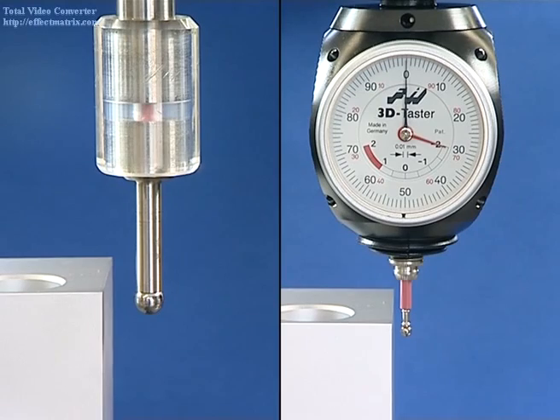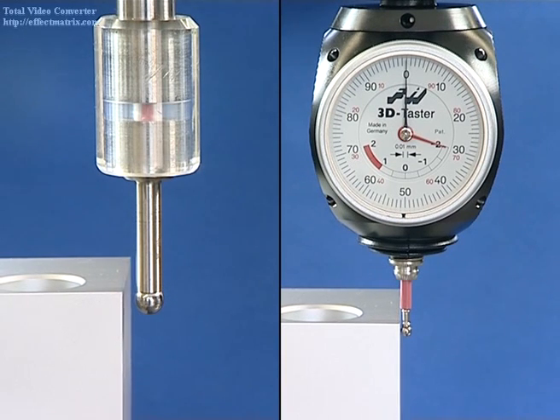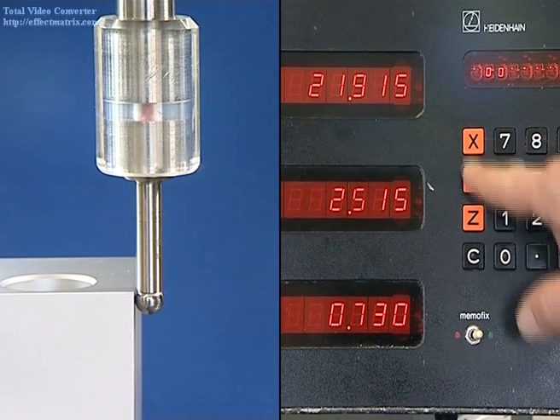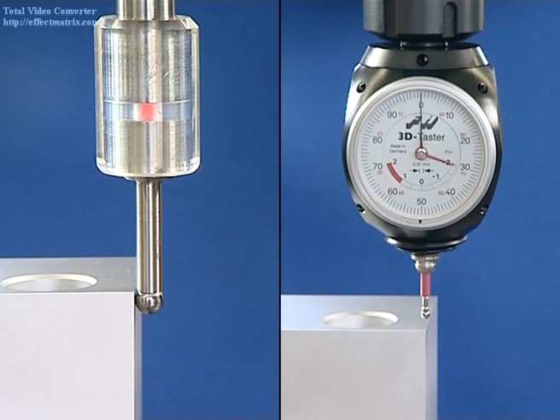The edge is approached with both sensors. For the Haimer 3D-Taster, the gauge starts as soon as the ball touches the edge. When the gauge is on zero, the spindle axis is positioned exactly at the edge. The unit compensates for the ball's radius. The measuring system on the machine for the corresponding axis is then set to zero.